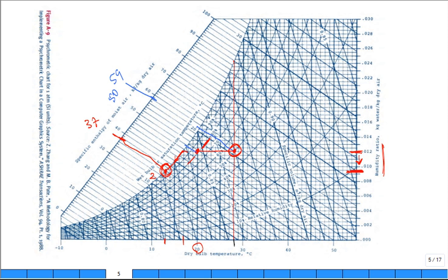Okay, so it goes from 59 all the way down to 37. That changes 22 kilojoules per kilogram. It's a much larger change, true? What was the temperature change between here and here? The first case, it was 8 degrees C, true? And then from 20 to 13 is another 7 degrees C. But almost the same temperature change, but a lot more heat transfer is required because you're condensing some vapor.